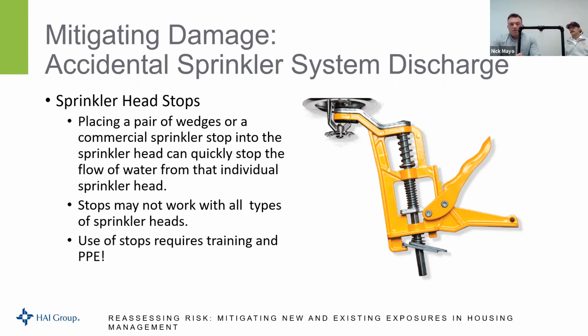So, sprinkler head stops. If we look at a sprinkler head, and everybody should be pretty familiar with a sprinkler head, the different parts of a sprinkler head, obviously we have the orifice, which is where the water flows through. This is the threaded part of the stem. This is the frame of the sprinkler itself. Stopping the water flow will be some type of plug. A glass fusible link will be what's holding that plug back. And then the deflector on the bottom is what determines how the water will be sprayed in the room. Some deflectors may be flat, some may be at a right angle or 90 degrees, depending on how they're installed and the way the water needs to come out.